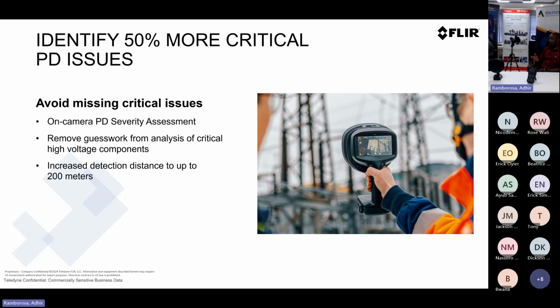Due to the sensitivity and the improved features of this unit, it can identify 50% more critical partial discharge issues. It will help you to avoid missing a lot of critical issues when you're doing the partial discharge inspection. It has an on-site, on-camera PD severity assessment. So once you're doing your inspection, you can see how severe that partial discharge is from the unit. It also helps you to remove guesswork from the analysis of critical high voltage components. It also has a greatly increased detection distance, so you can detect a partial discharge from as far as 200 meters. Something that we have seen a couple of times in the inspection. Definitely have.